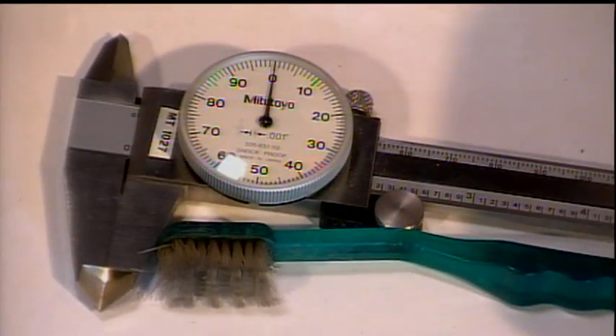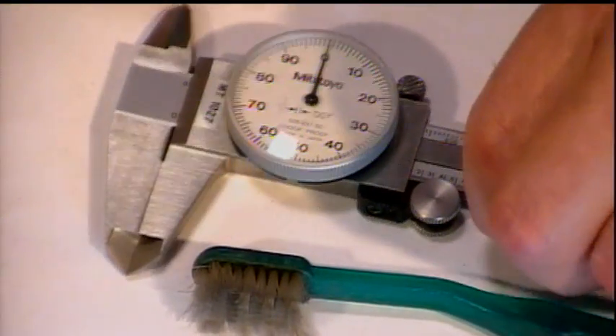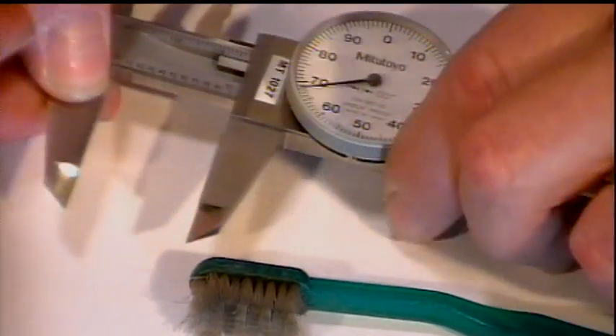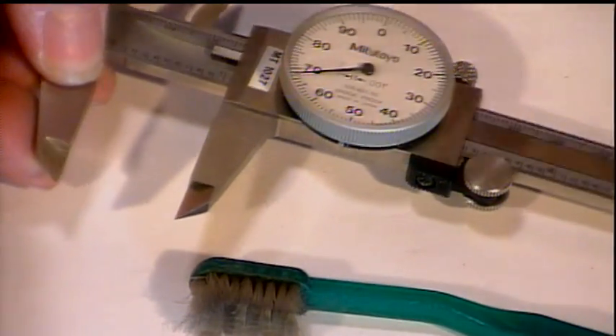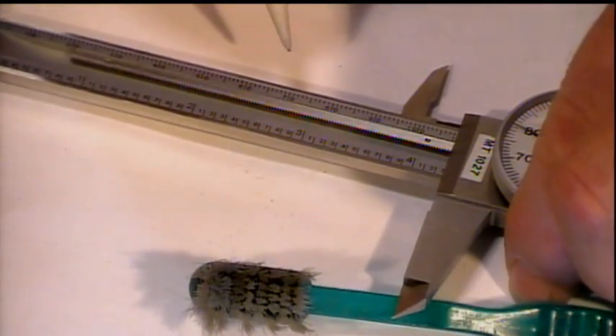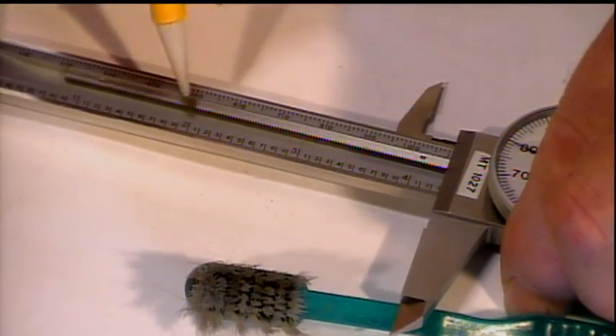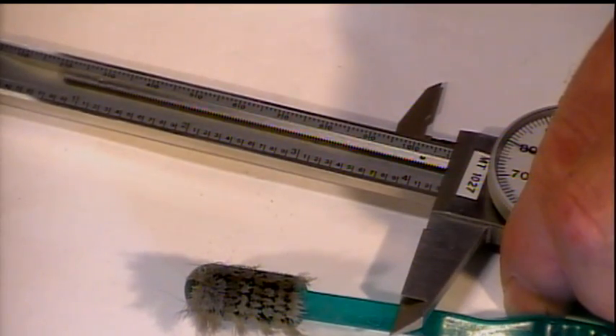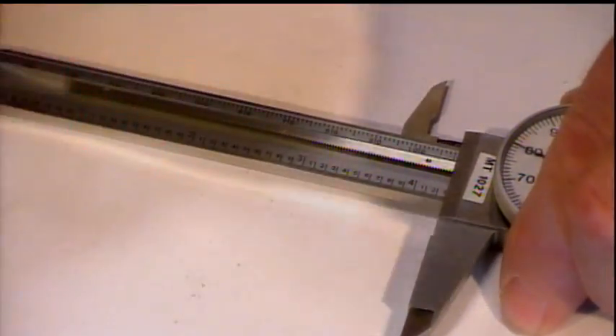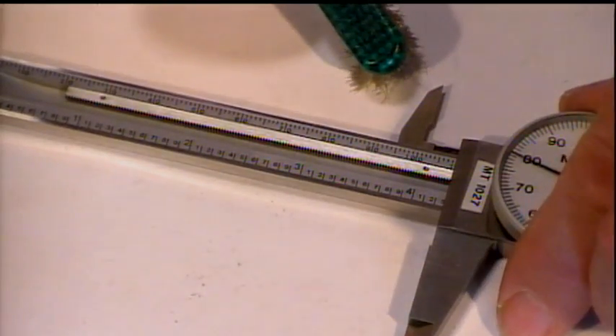Here's one of the essential tools that every good calibration lab has. It's a toothbrush. Hey, that looks like the one I use. Typically, dial calipers work on a rack. And there's a rack in here that the gears will ride on. And that rack is just notorious for collecting chips and dirt and grease and oil. So that would cause the indicator to skip a cog, right? Skip. Okay. And a lot of times when they're not on zero, when you close it and it's at 9 o'clock or 3 o'clock or 6 o'clock, that's what's happened. It's skipped a tooth.